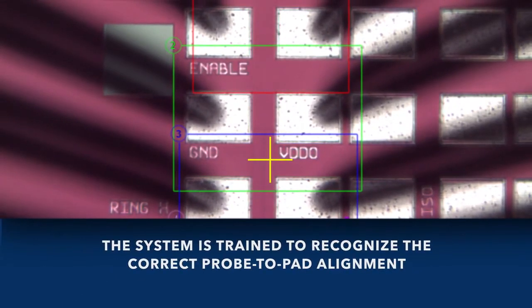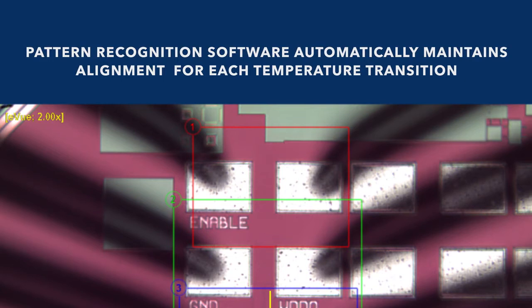It starts with our ViewTrack software in combination with our eViewPro microscope technology. This assures constant contact quality on small pads. First, the system is trained to recognize the correct probe-to-pad alignment. Once the correct alignment is determined, pattern recognition software helps position the probes to maintain this alignment as the temperature set changes.